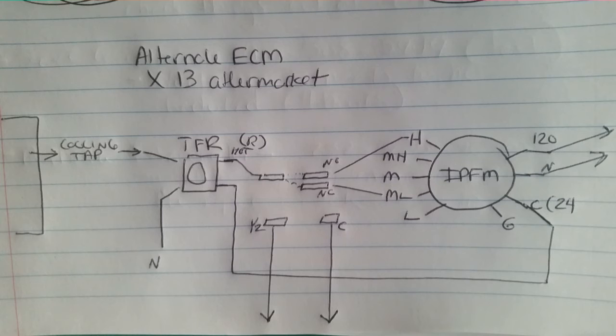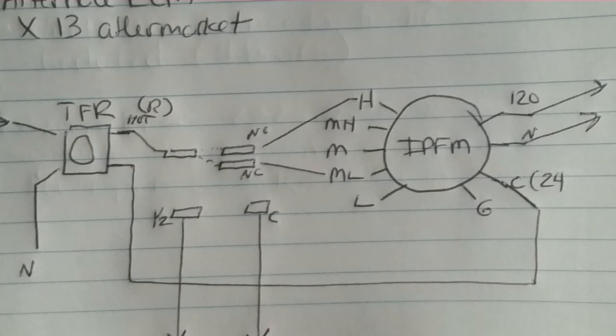So instead of switching high voltage between cooling tap, normally open, normally closed, we're switching low voltage. Our cooling tap, which used to produce 120 for the PSC blower, is now producing 120 for the transformer, which is producing 24 volts, so it can power the ECM motor or get it started. So let's say we'll have 24 volts on hot going to the cooling tap side of the relay. Normally it will be going to normally closed, which is medium low or low speed cooling. When we get a Y2 call, our relay will switch to normally open and go to high speed cooling. Again, you may have to tamper with this to get the right airflow. This is just an example. And this is one way where you can use the original controls and add on a couple items so that you can use a 2-speed cooling system.